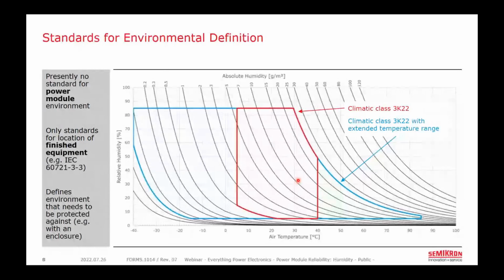Presently, there's no commonly accepted international standard defining the microenvironment around the power semiconductor module. The best we have is something like the IEC 60721 series of standards that classify the external macro environmental conditions that a finished product will be subjected to in operation. And so what we're showing here is a recreation of that climatogram from IEC 60721-3-3, which classifies environments for equipment in a stationary weatherproof location. Different environments are then defined by different climatic classes, one of which is plotted here in red.